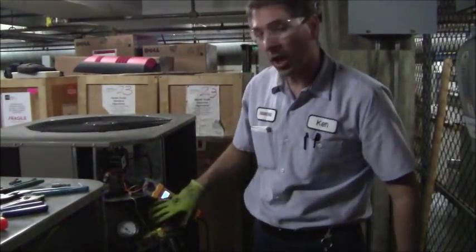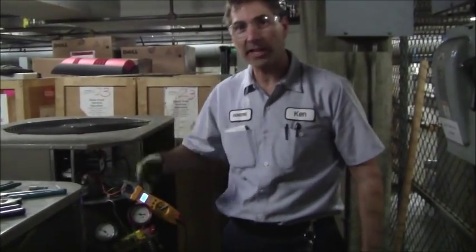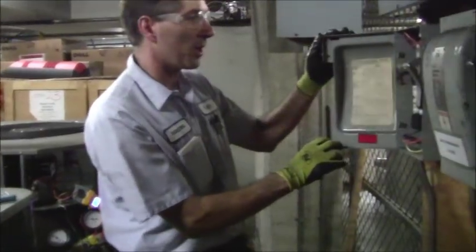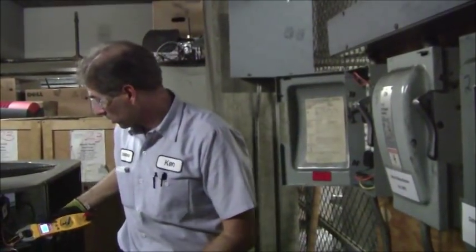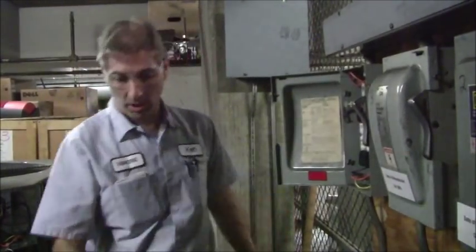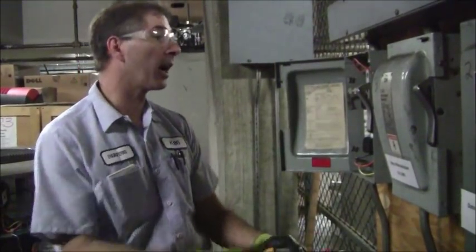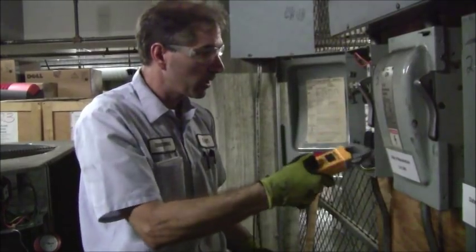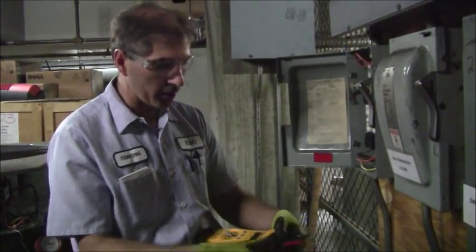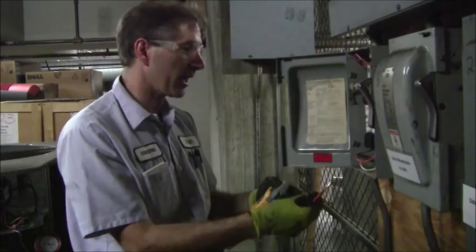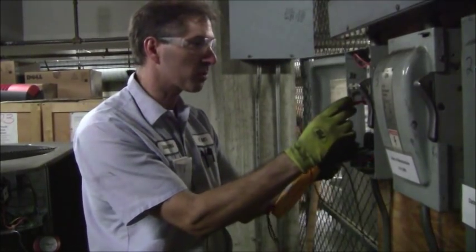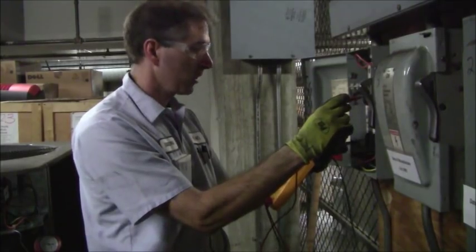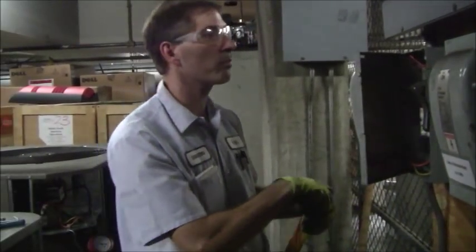I thought I was going to have enough time to actually go through it a little bit better, but apparently not. I wonder if I blew another fuse. So when you want to check your fuses, I'm going to go ahead and I'm disconnected here. I'll do an NCV. It's all dead. I'm going to go ahead and do a continuity check. So when you touch it, you get continuity. This was the fuse that was blown before. Now, all three fuses are good.